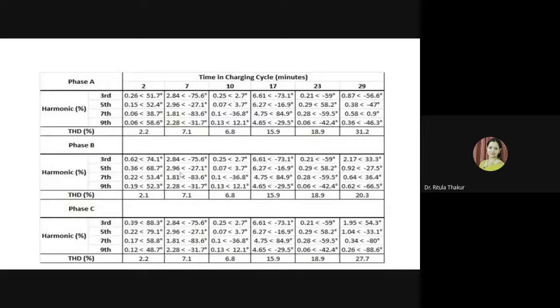And if we talk about the comparison of these harmonics from the initial stage to the final stage, you can see that it varies from 2.2%, where it is almost nil in the beginning of the charging, to 31.2%, which is quite a big figure. And it is a cause of worry. We can't ignore this fact. Similarly, we can observe for phase B also, 2.1 to 20.3, and then 2.2 to 27.7.